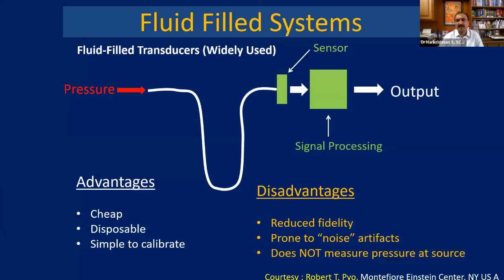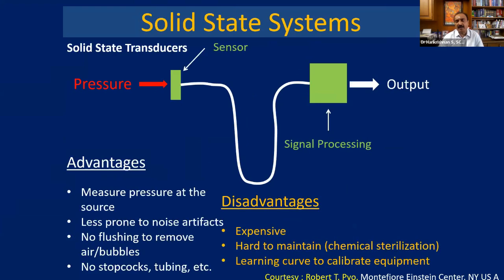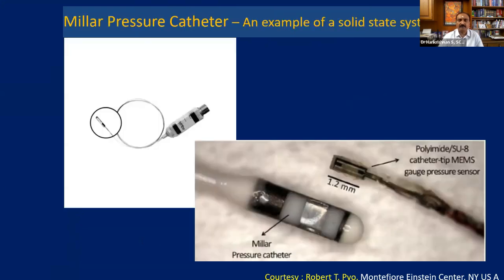We usually use the fluid filled systems in the cath lab. The advantages are they are cheap, disposable, and simple to calibrate. The other type of pressure measurement systems are the solid state systems, which are hardly used for pressure measurements, except in the case of an FFR, where it is a solid state system. If you are asked, you can say that the Millar pressure catheter is an example of a solid state system. This is not routinely used.